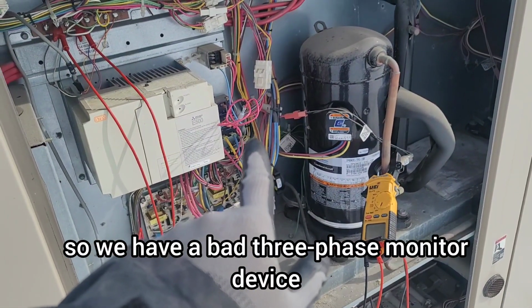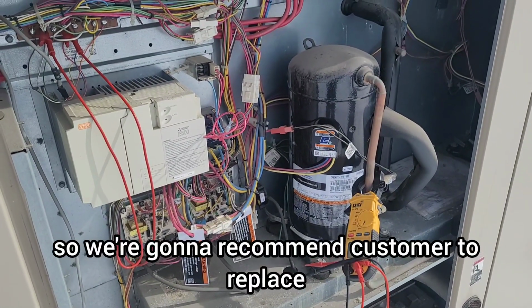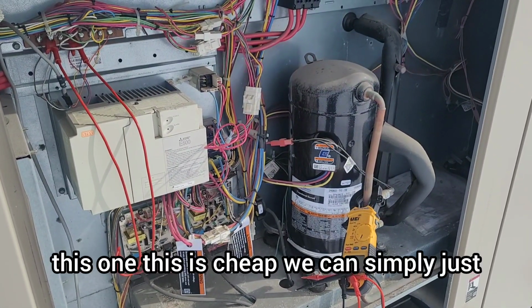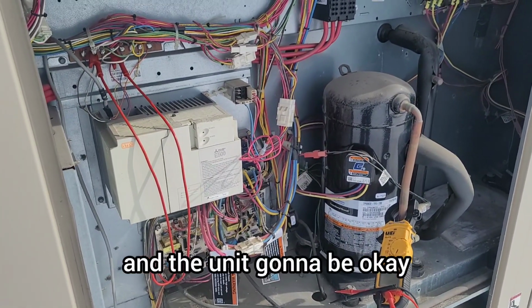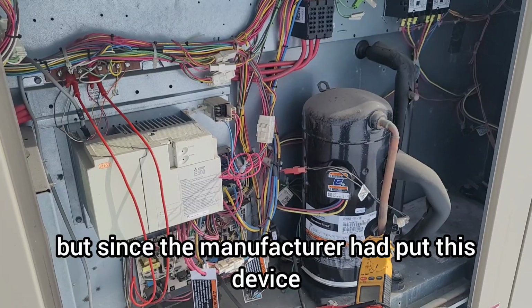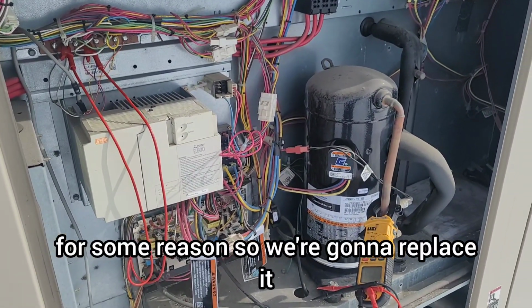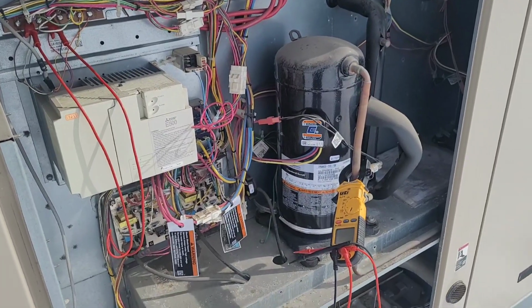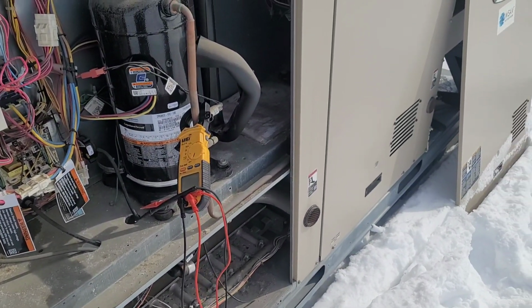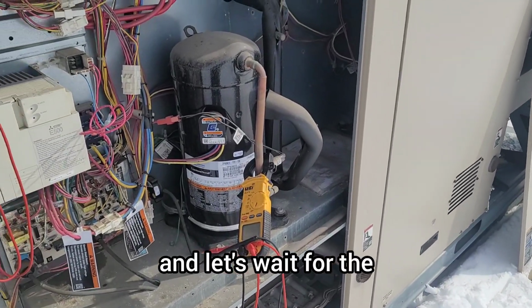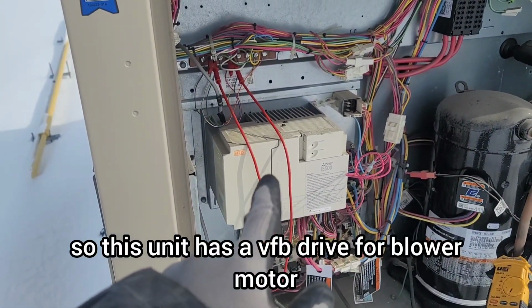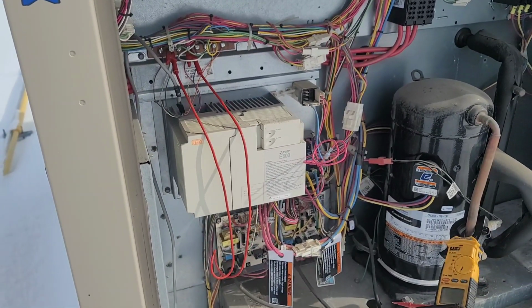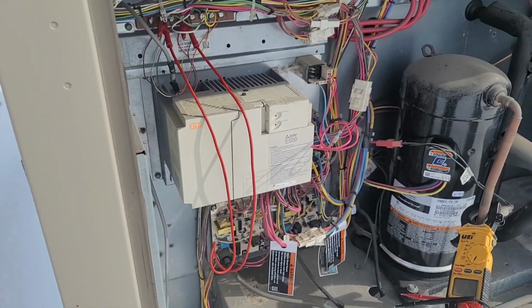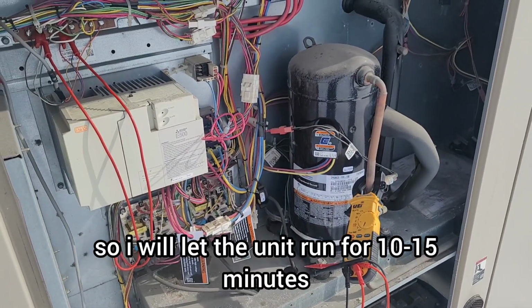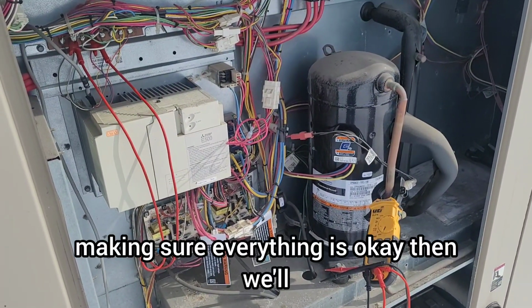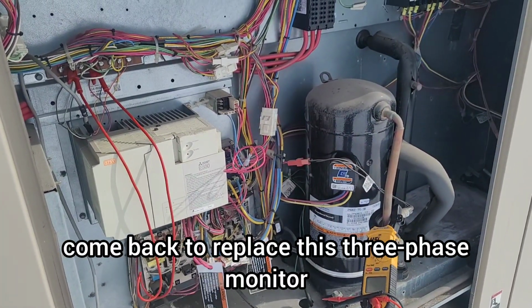So we have a bad three-phase monitor device, so we're gonna recommend the customer replace this one. This is cheap. We can simply just jump between these two wires and the unit is gonna be okay. But since the manufacturer had put this device for some reason, we're gonna replace it. It's not much expensive. Okay, we have ignition, and let's wait. This unit has a VFD drive for the blower motor. So I will let the unit run for 10-15 minutes, making sure everything is okay. Then we'll come back to replace this three-phase monitor.